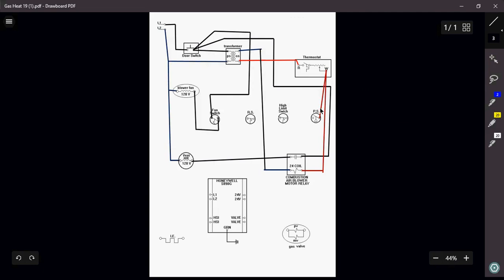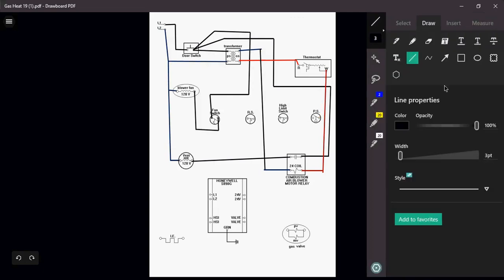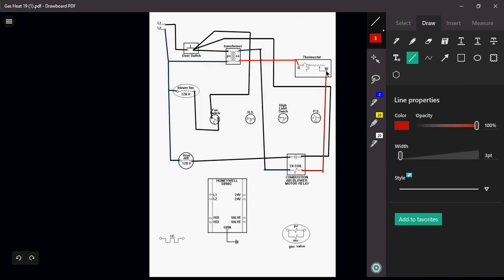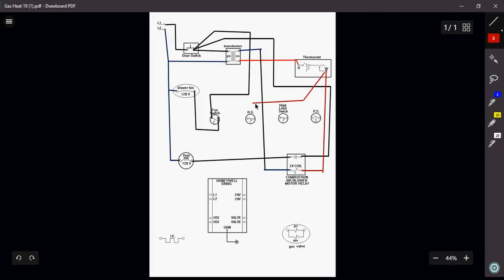Okay, I can take this wire and I can go the other way. Again, all they are safeties. So I can come out of my W if I wanted to. I can go through my rollout switch first if I want. Then I can go through my high limit switch. I can go through my pressure switch if I want. It does not matter. They're switches. Just as long as they're in series, they're good to go. Okay? So out of my pressure switch, I'm now going to send that wire down to my ignition module on my 24 volts, just like that.